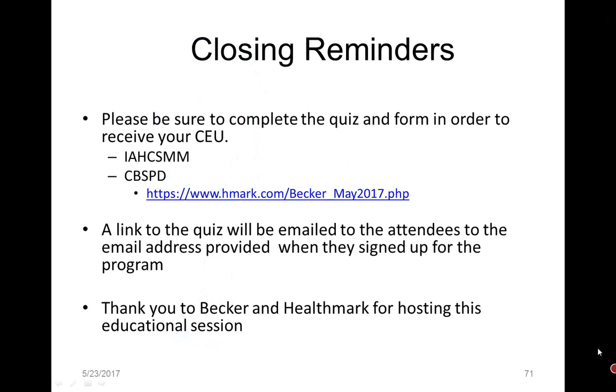Are silicone mats and holders compatible within the ultrasonic machine? That's a two-part question. The first one is check with the company of the silicone mat if it's supposed to go in the Sonic with instruments or by itself, but silicone absorbs sonic activity. So in my opinion, the silicone mat should not go in because it will absorb the cavitation.